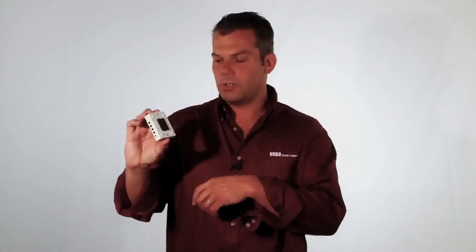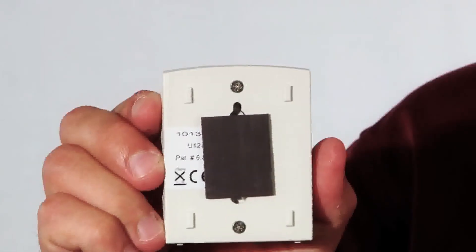The logger does have a user-replaceable battery. You unscrew the two screws on the back. The battery's good for about a year. It has the ability to record up to 43,000 measurements. In real terms, if you're recording every 15 minutes, it'll run for about 113 days. And through the HoboWare software, you can turn off channels to maximize your memory.